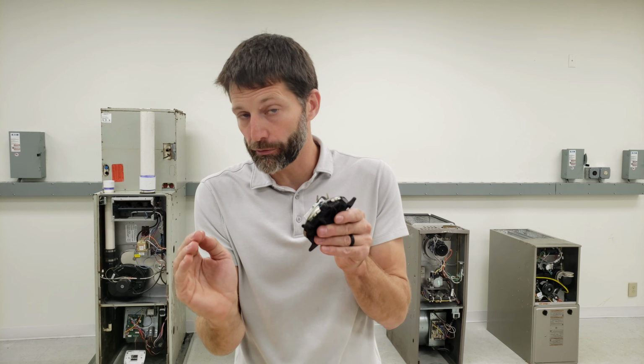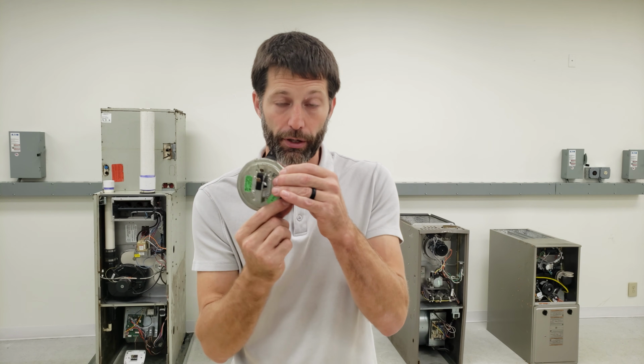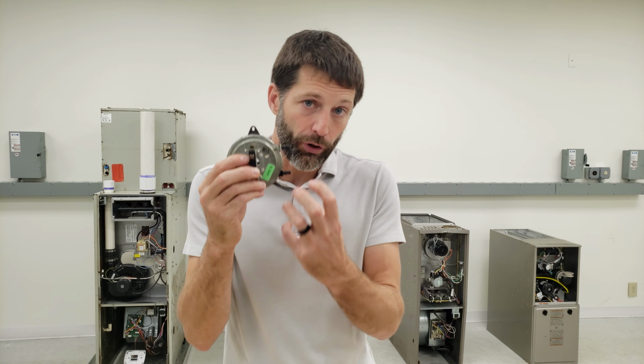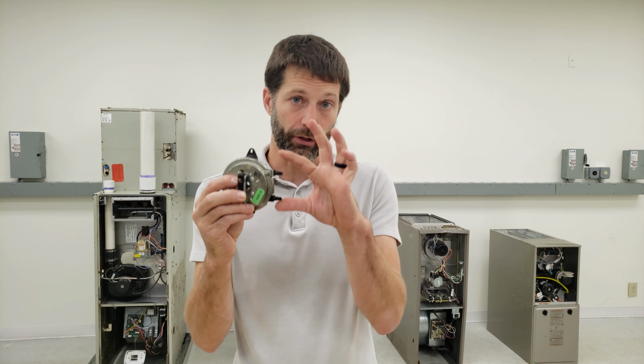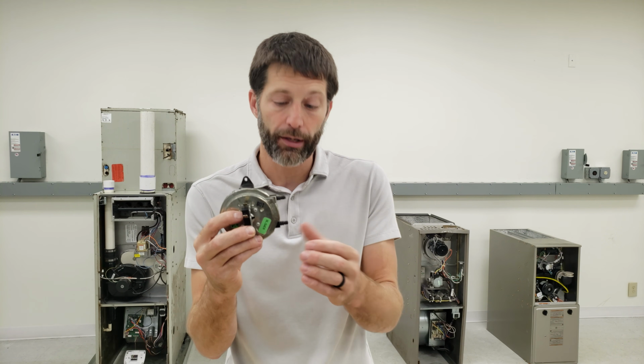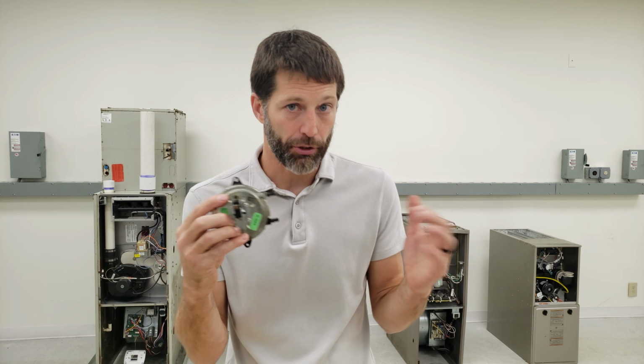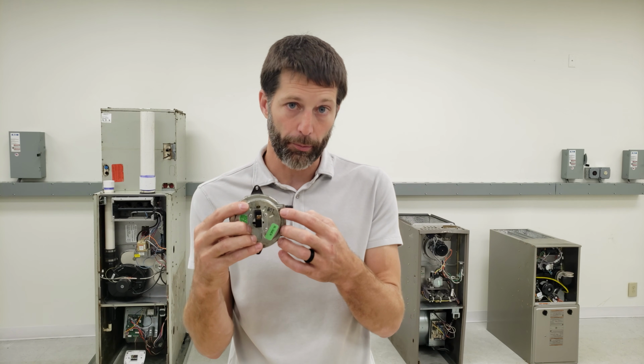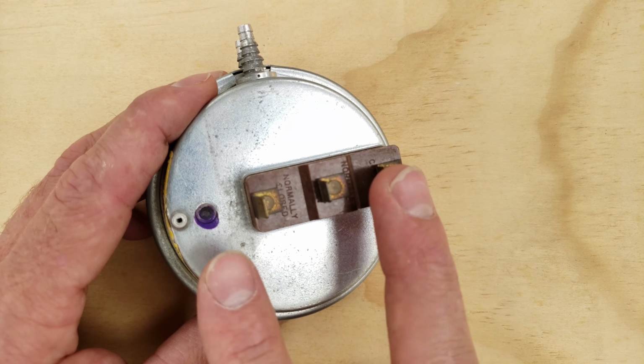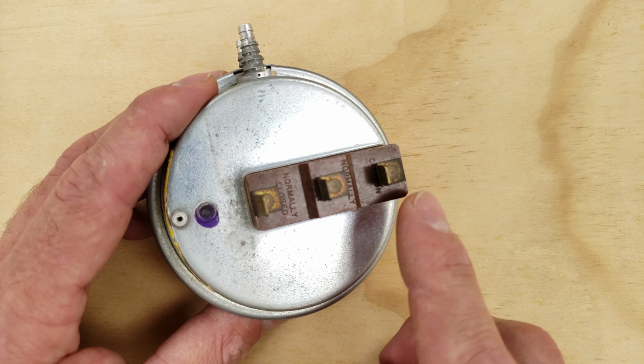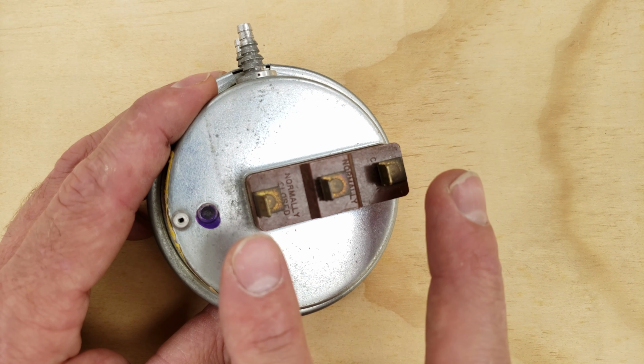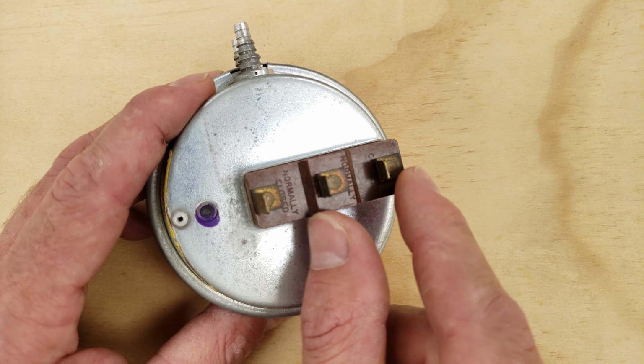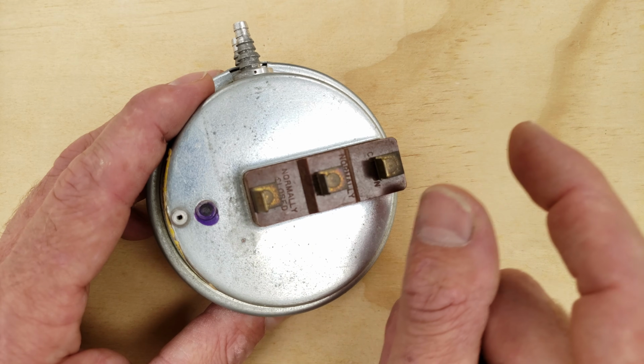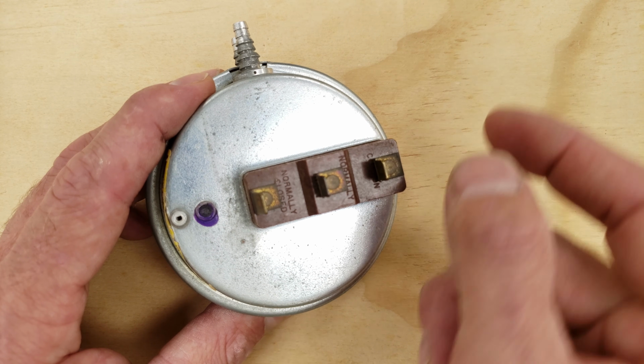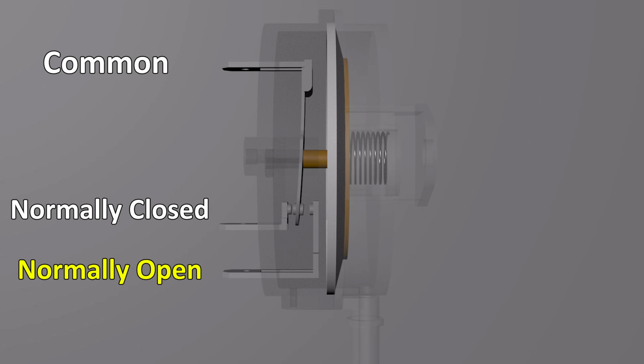And so what you also want to remember is the negative port of the pressure switch always has a lower overall pressure than the positive port, but they're both lower than atmospheric pressure while the system is running, and the positive does not have a pressure greater than atmospheric pressure. They're both lower than atmospheric pressure, so you're just looking for your differential. So on this pressure switch, you see we have 3 tabs. You have a common connection point, you have the normally closed set of contacts like this, and then you have the normally open set of contacts like this. When the inducer motor is running and there's a pressure differential across the switch, the normally open contacts right here are going to close, and the normally closed set of contacts are going to open up.